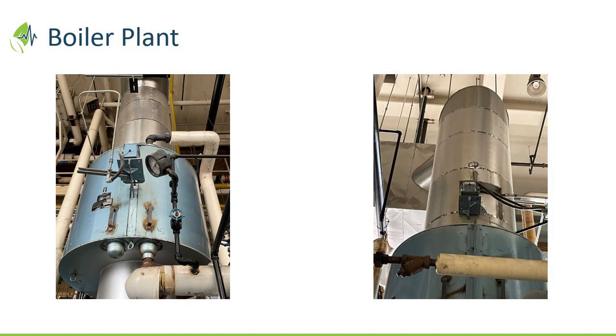So for those boilers with the stacks, do you still need the giant stack if you retrofitted forced air fans? So therefore, you just don't need the stacks anymore, but you just have them because they're there. I mean, someone designed the draft on that boiler plant a long time ago, and it's got as much to do with the performance of boilers as it does with the architecture in the area. So Southlake is a giant horseshoe type building, and there are some very bizarre wind patterns that can occur there. So I suspect that's why the stacks were designed the way they were when they were put in. But I know a lot of your hospitals, and some of you have retrofit into old brick radial stacks just because it was there, it was easy to put a liner in, it provided satisfactory draft.